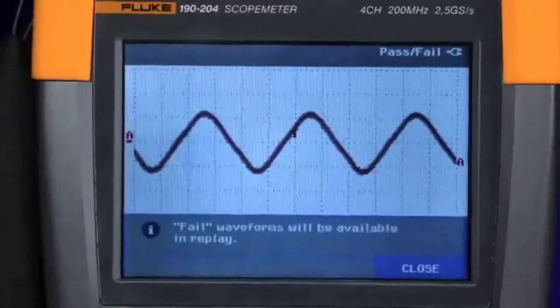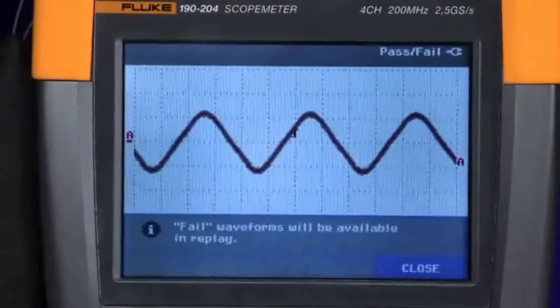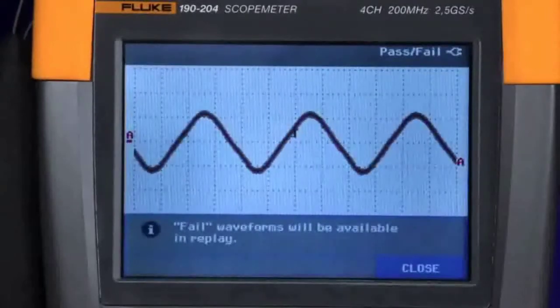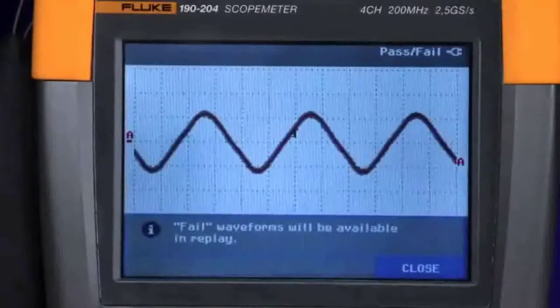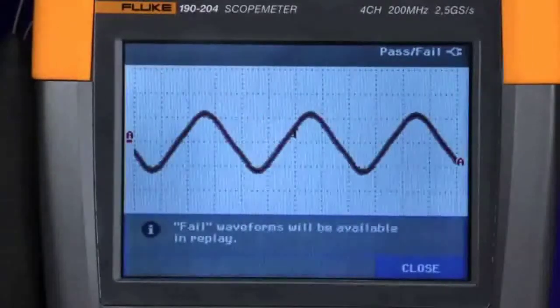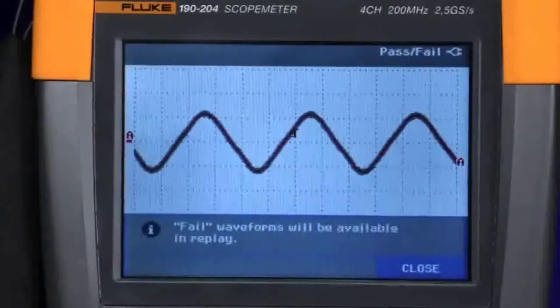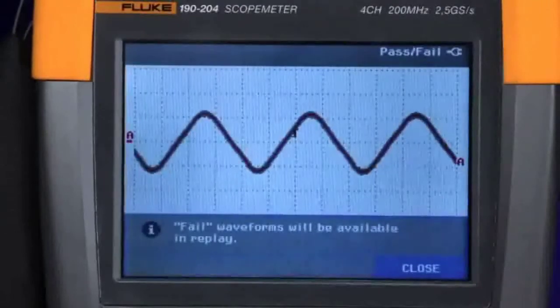Any time a trace falls outside of that plus two pixel window, it will immediately capture that screen and store it to the replay memory. In the replay memory, we have a buffer of 100 screens where you can store up to 100 events on a first in, first out basis.